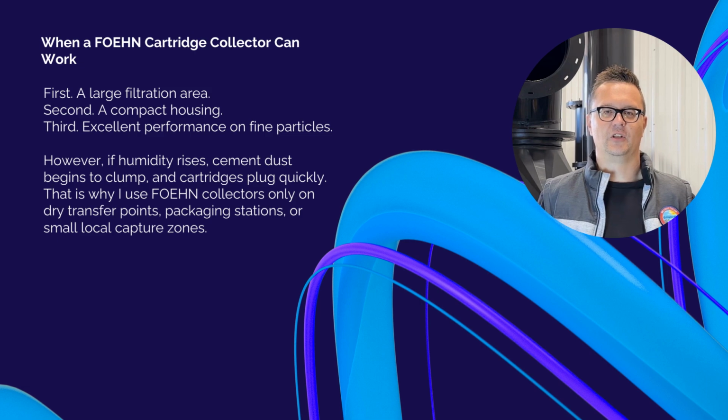When a cartridge collector can work. Cartridge collectors perform very well, but only if the dust is completely dry. They offer several advantages. First, a large filtration area. Second, a compact housing. Third, excellent performance on fine particles. However, if humidity rises, cement dust begins to clump and cartridges plug quickly. That is why I use cartridge collectors only on dry transfer points, packaging stations, or small local capture zones, when a cartridge collector can work.